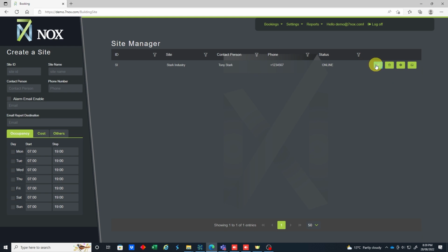If you're using 7NOX to schedule after-hours services, then you would select the days and times which make up your normal business hours. Ticking these boxes will determine those hours. The Get Daily Schedule function would then pull those selected days and times into Niagara. However, if you are using 7NOX as a simple scheduler for booking rooms at any time, then you would leave these boxes unticked. This would essentially tell Niagara that there are no normal business hours for your site and that tenants are open to book services at any time and day.